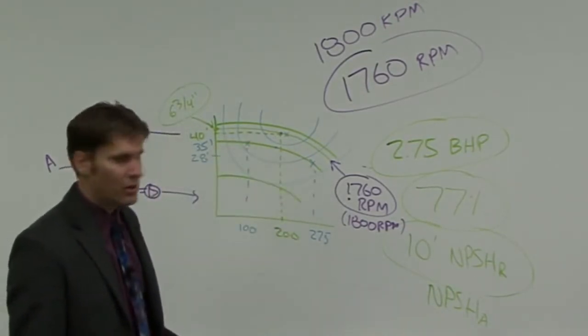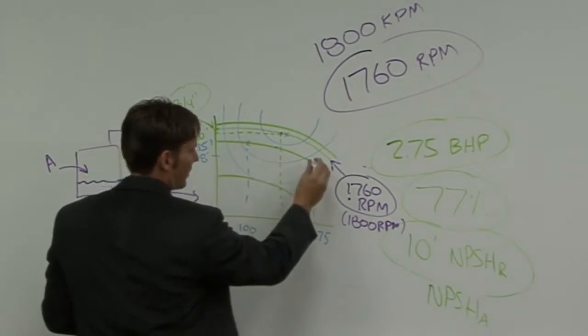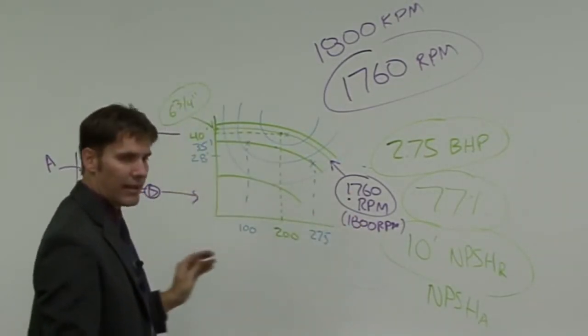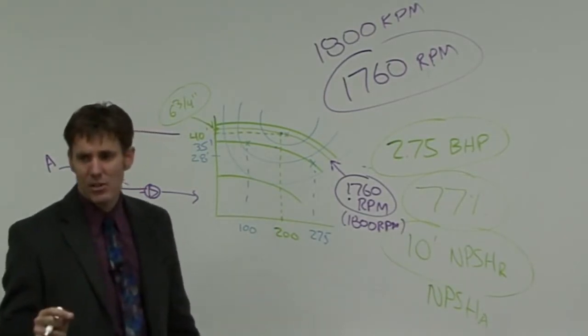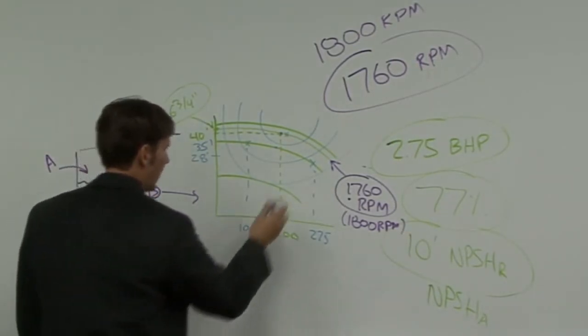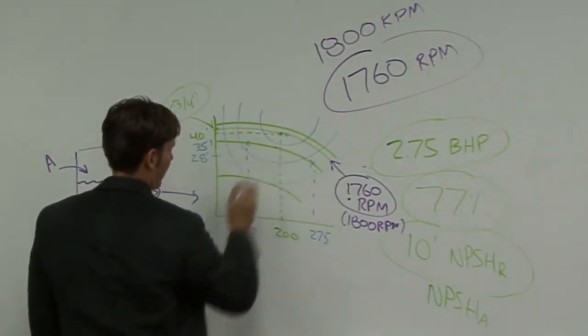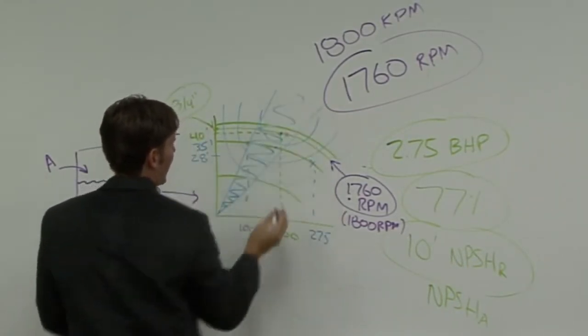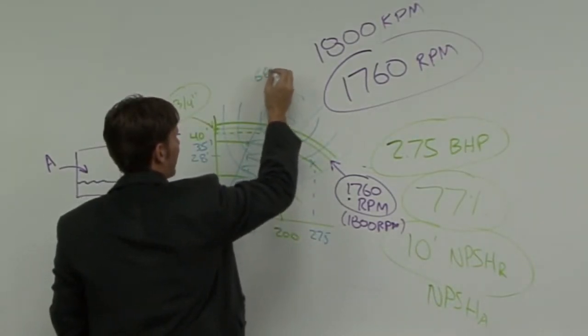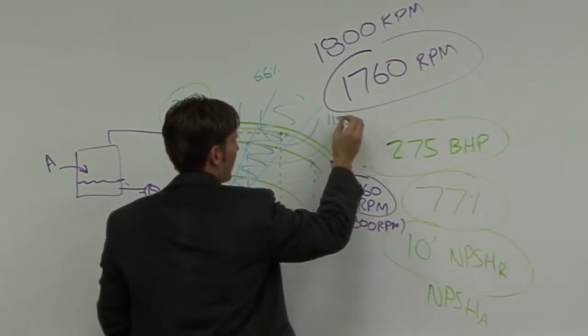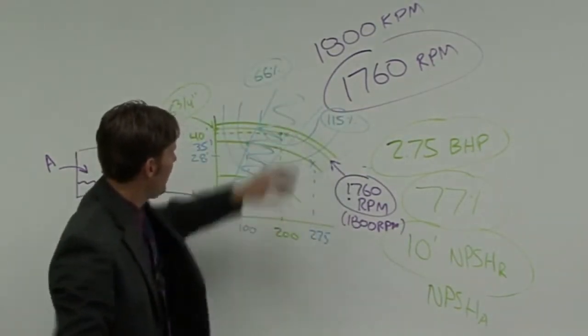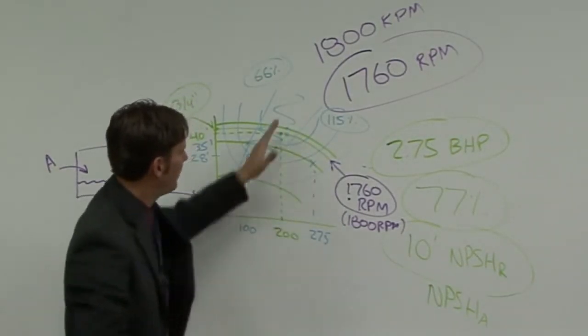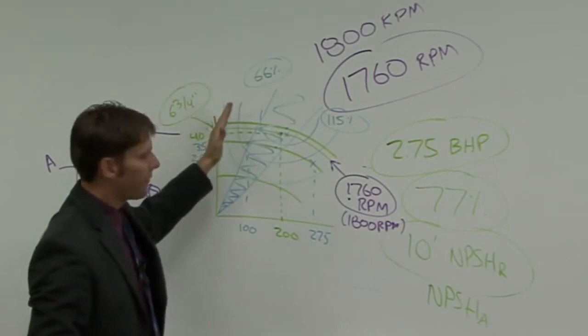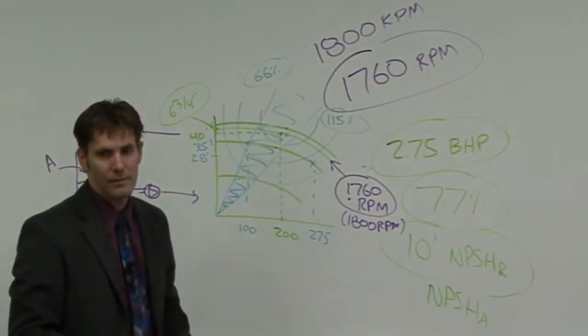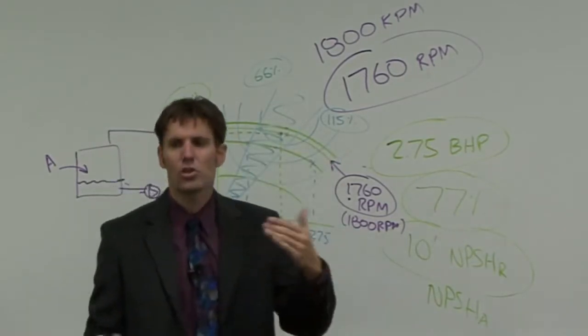Where do I want to pick my pump curves? We need to limit ourselves on where we select, because this is way out to the right and this is getting way back to the left. Well, ASHRAE gives us some recommendations of where we should select our pumps. First of all, they tell us a window that looks something like this, with my best efficiency point here. This is a good selection range, and you want to pick something within this range. That is 66% to 115% of our best efficiency point. So if my best efficiency point is right here, then I can be 15% greater than or 34% less than my best efficiency point. That gives you a good guideline of where you should try to select these pumps.